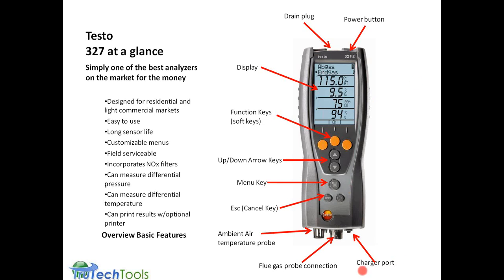Next over is the charger port, where you'd plug in, and I'm sure if you've had your meter or you're looking at getting one, you can use the charger port to plug in and to either run the meter or, usually more often, to charge the lithium ion battery that's inside. And I believe you get about 5 hours of life typically, depends upon how you run the meter, but you get about 5 hours of life out of the one charge in the battery. The charge also displays on the screen the percentage charge when you plug it in, so you know how far along it is in the charging process. There's a differential pressure port also at the bottom that would allow you to take the minus side of pressure if you wanted to do some differential pressure measurements, as we talk about up here.